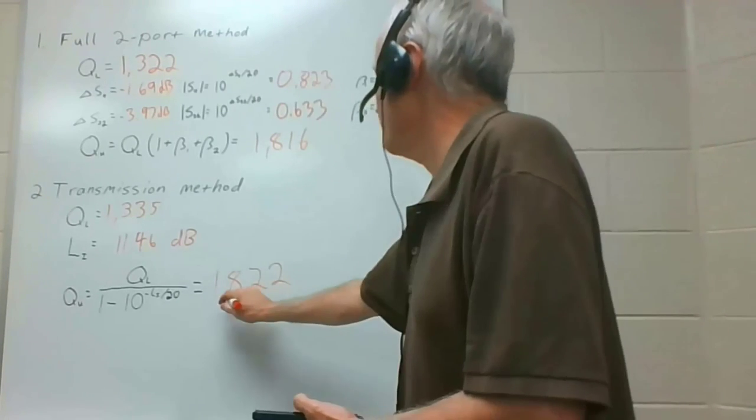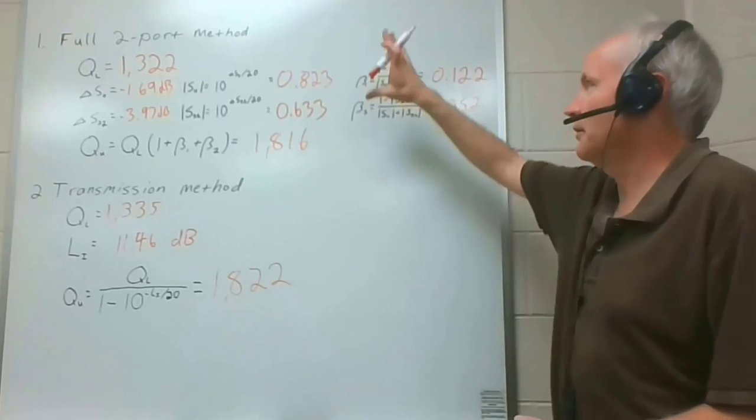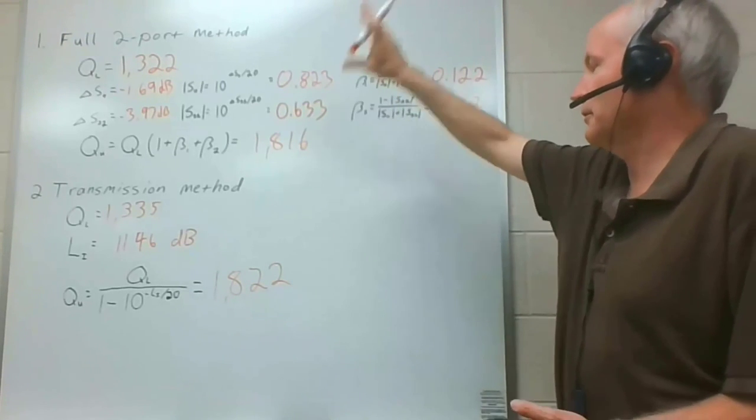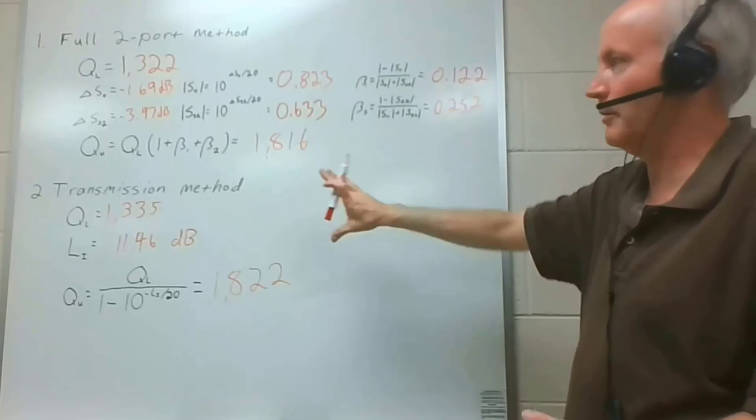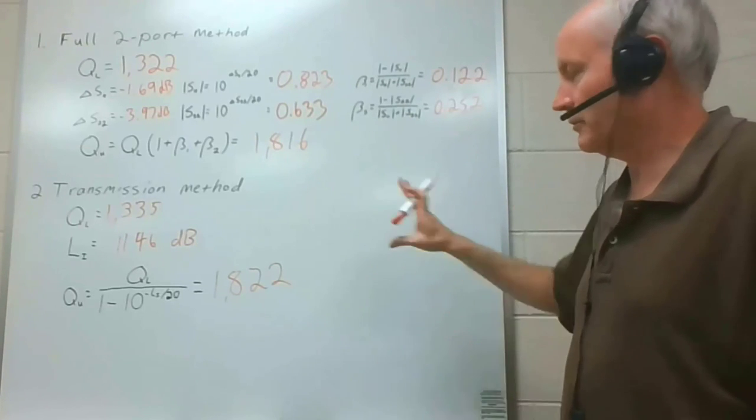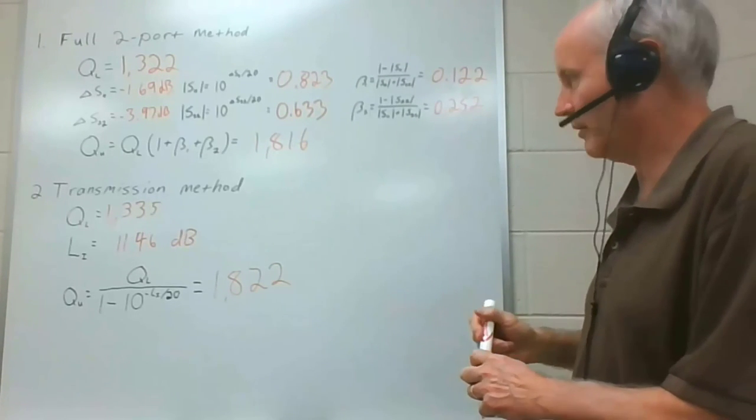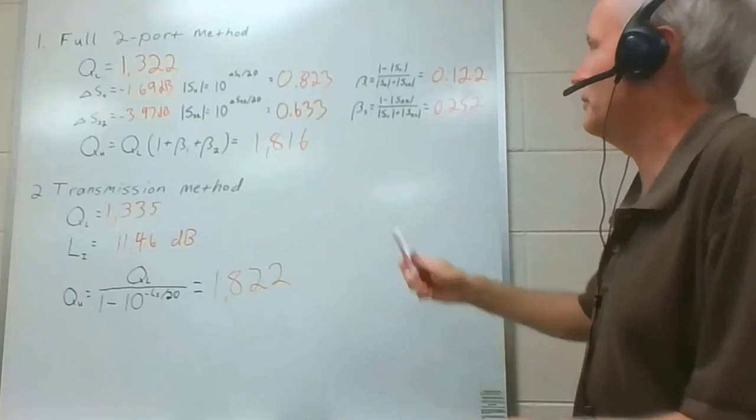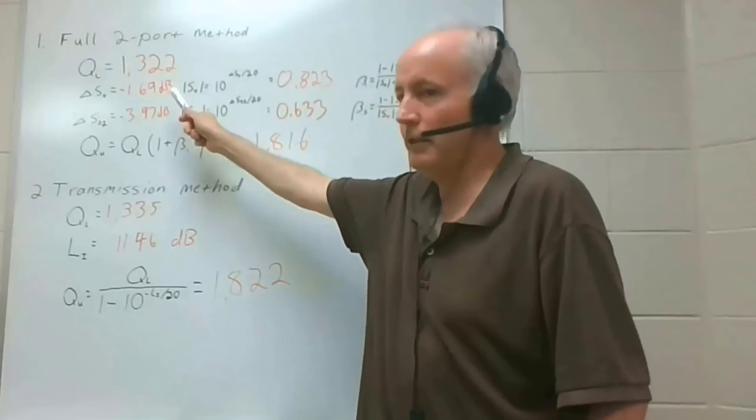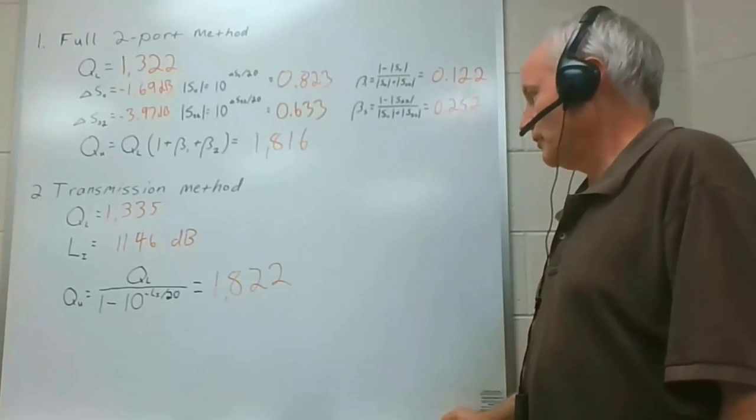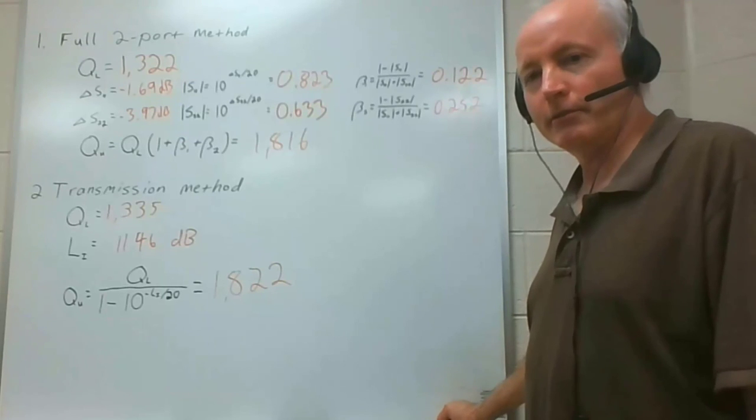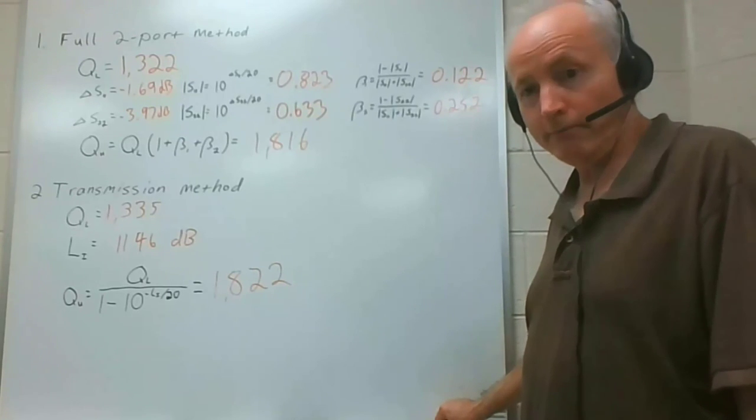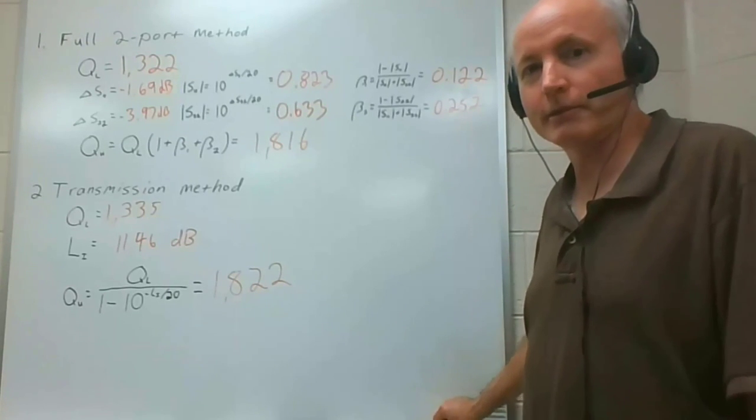So there you have it. The unloaded Q measured with the full two-port method gave 1,816. And pretty much the same number using the transmission method. There's the plus or minus on all of those which you could propagate through if you estimate the uncertainties and the return losses. Next time I'll talk about how to measure the unloaded Q when you only have one port available in the resonator.